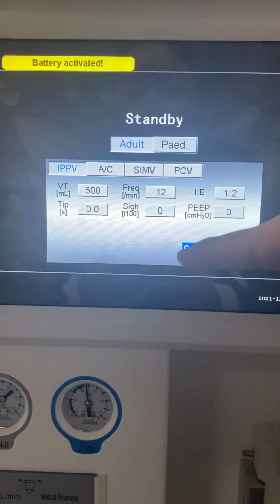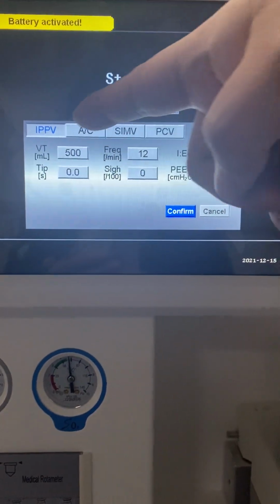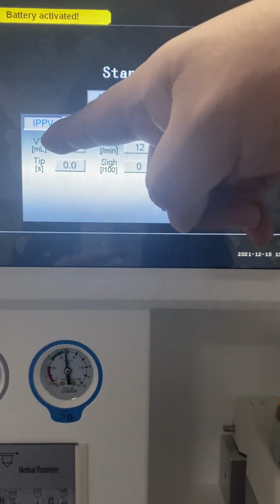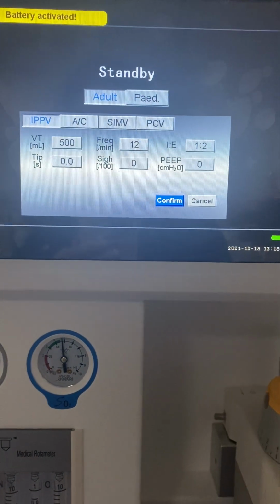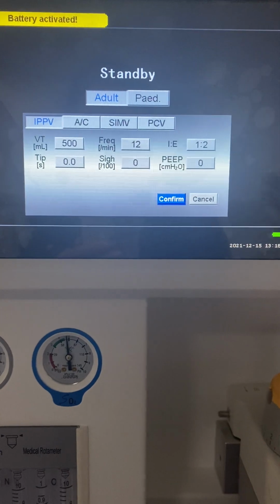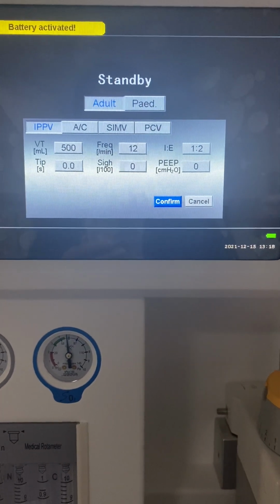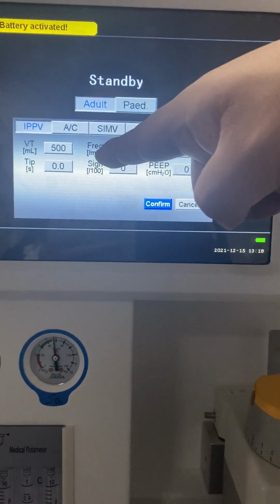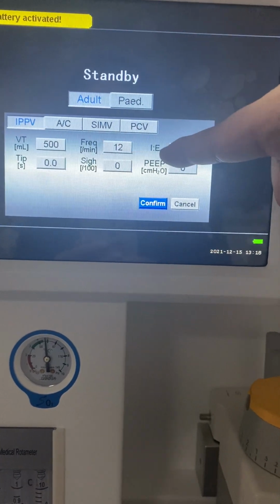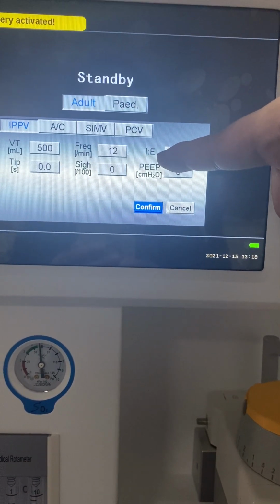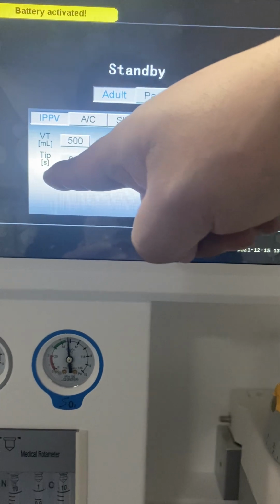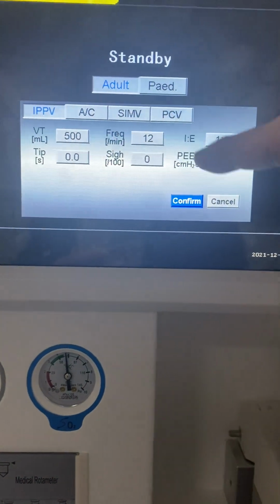Now under each ventilation mode, we can see there are several parameters. The most important are always in the first column. For example, under IPPV, we see VT, which means tidal volume. It is always set according to the patient's weight. The second one is the breathing frequency. Then the inspiration and expiration ratio, the inspiration time, sigh, and PEEP.